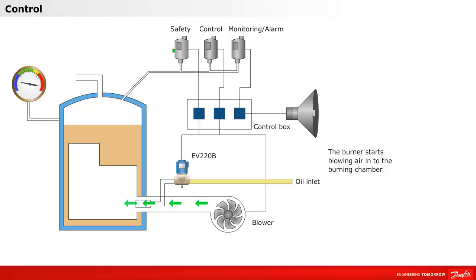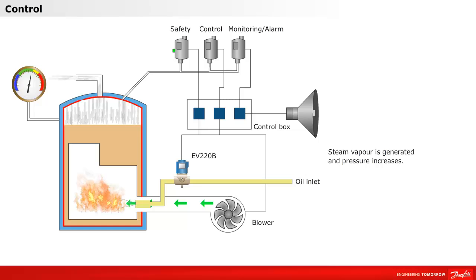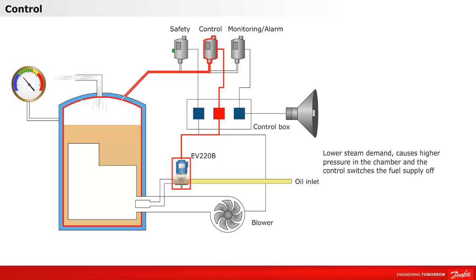Let's look at an example of a typical control function application. The burner starts blowing air into the burning chamber. Oil is sprayed into the chamber and is ignited. The heat increases and steam is generated. Steam vapor is generated and the pressure increases. The lower steam demand causes higher pressure in the chamber and the control switches the fuel supply off.